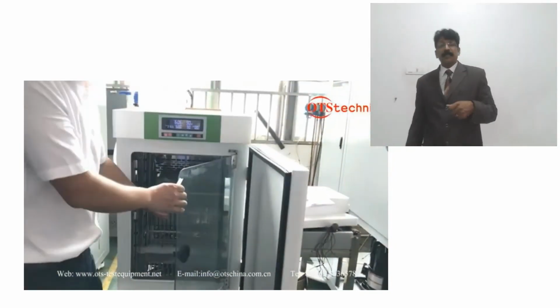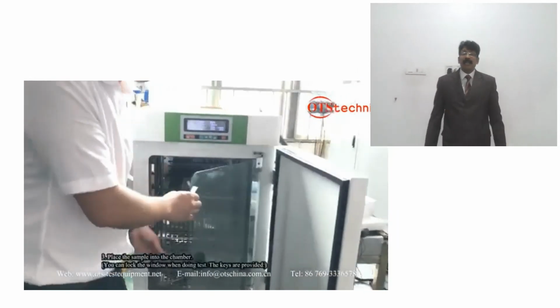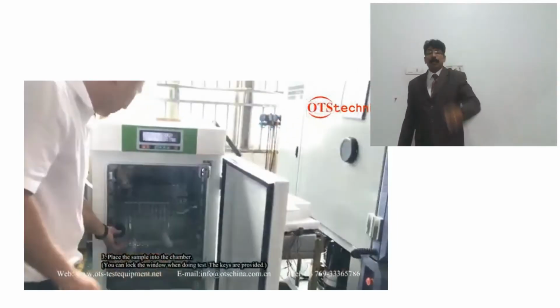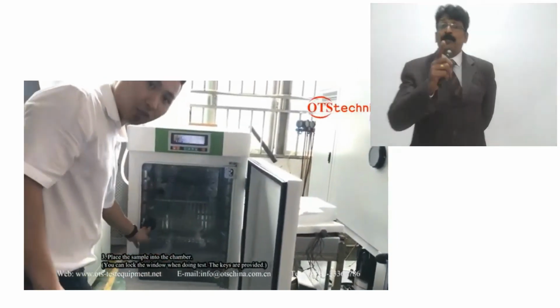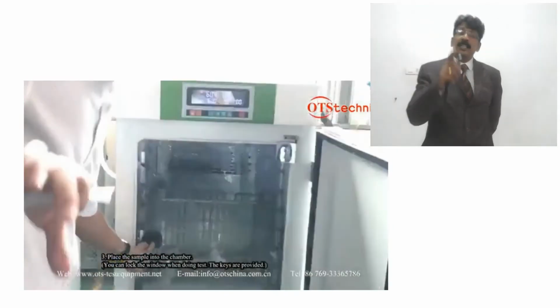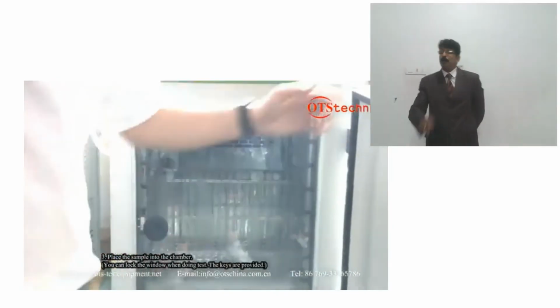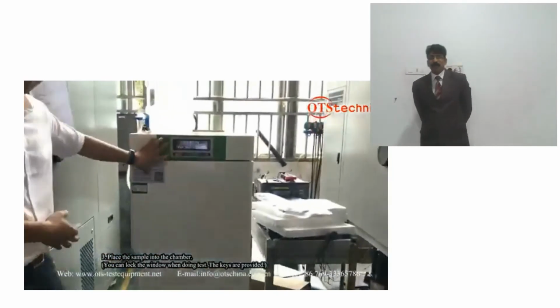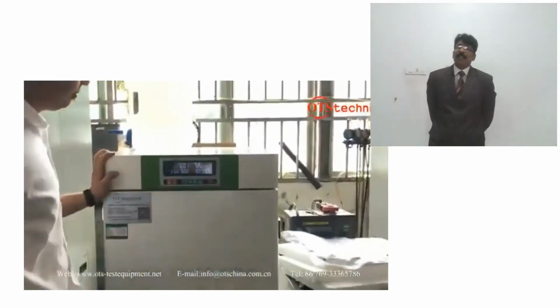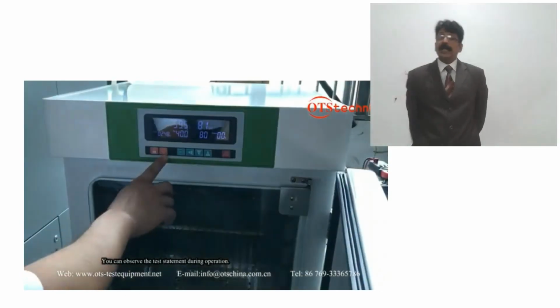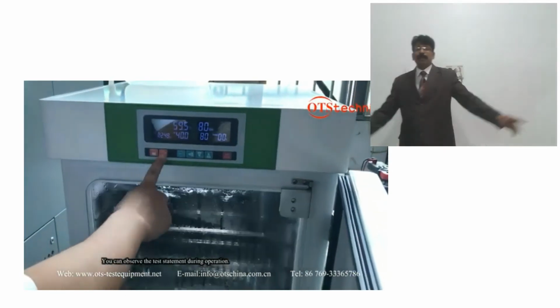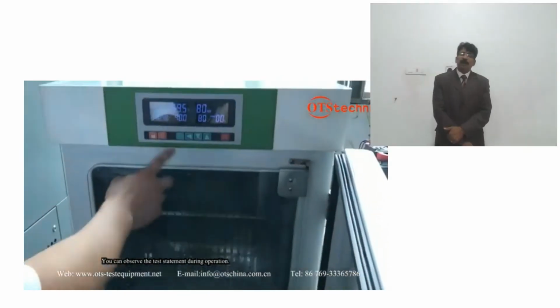There are some spaces where we can keep the samples everywhere, and you can find out which rack and which place you have kept them in. These all have to be denoted in the display. Also, in the computerized version we can make it very clear what type of samples there are, even if it is a very large stability testing machine.